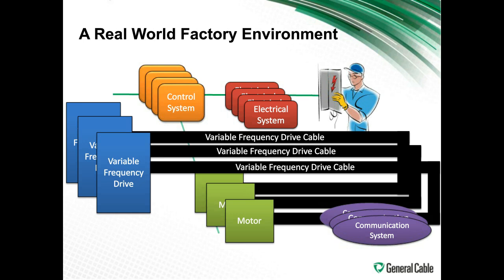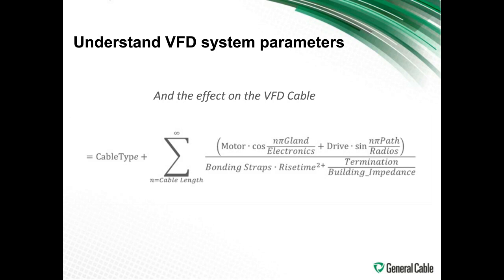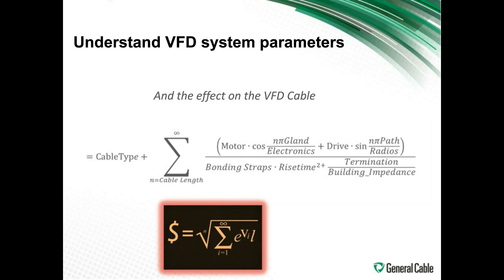So how do we take care of that chaos? You have to manage it and have a good design. To do that, we have to understand the system parameters and the effect that the drive has on the motor, and then the effect it has on the cable itself that connects the two. This is kind of a mock way to show the effect. You have the cable length as part of this equation, the type of cable, the bonding, the motor type, the rise time that is created by the variable frequency drive, and the termination. All of these can cause issues. So altogether, you can have a formula that's creating evil and increasing cost if you don't take things into account to take care of these issues.